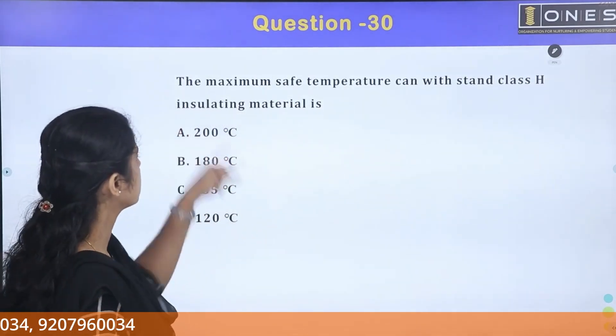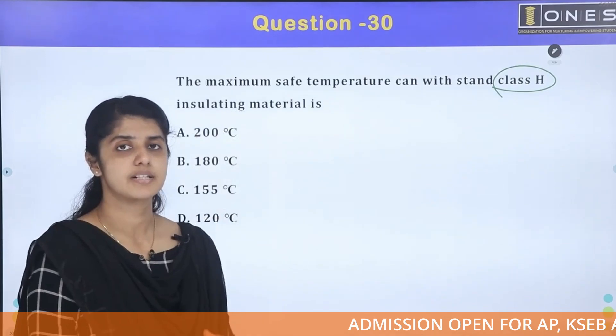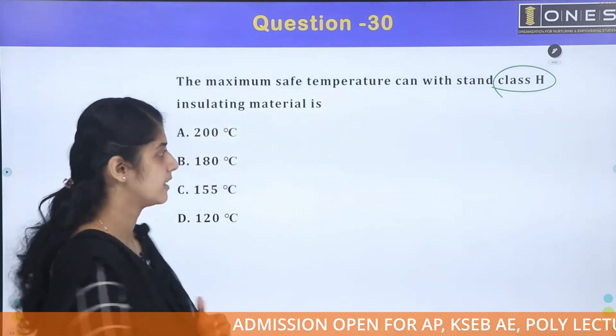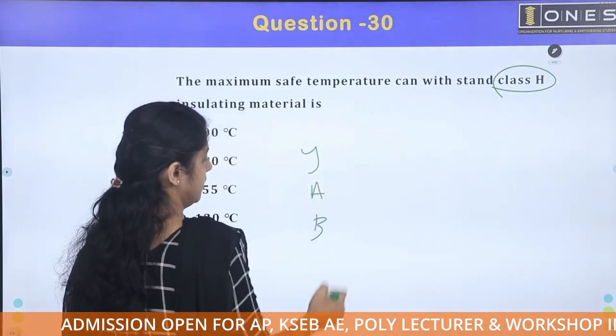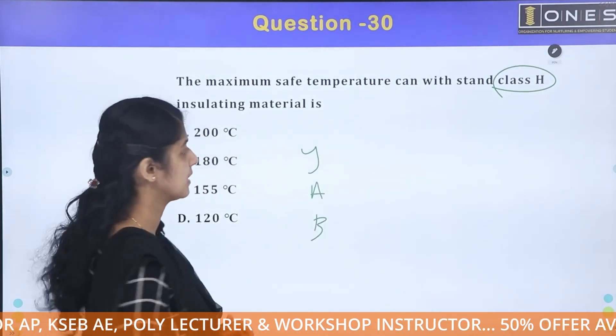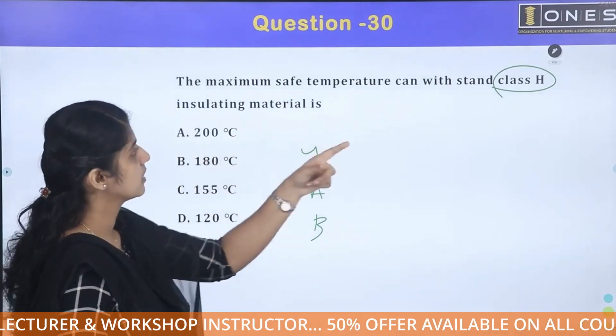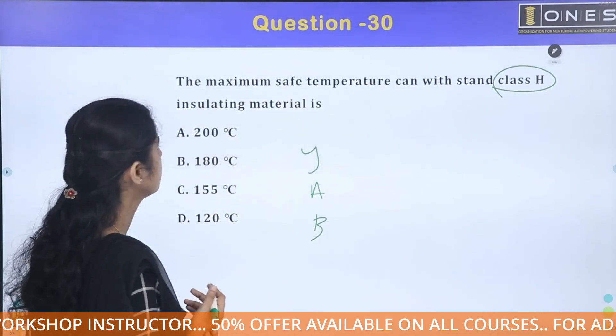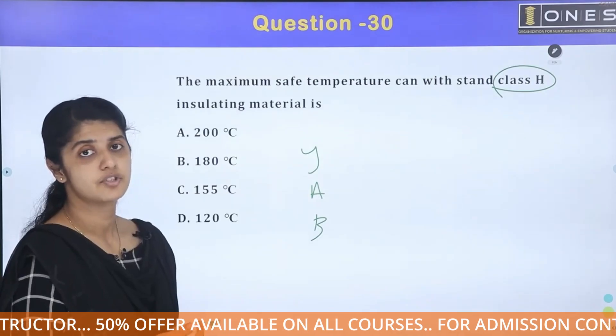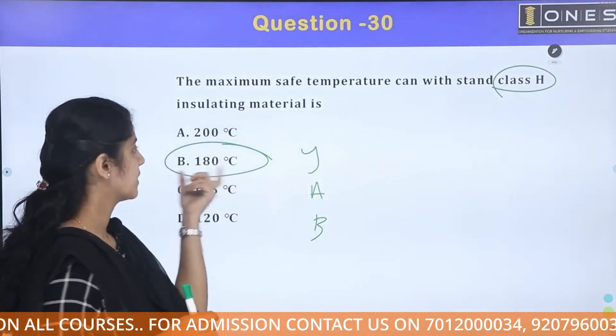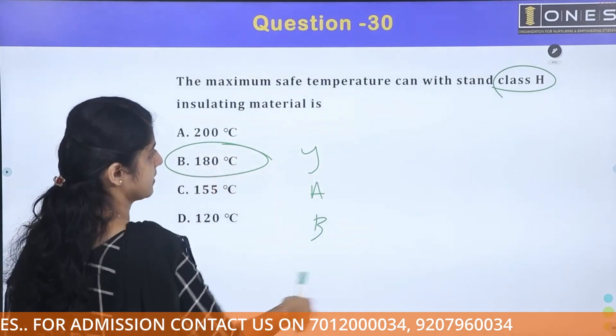The maximum safe temperature that a Class H insulating material can withstand — insulation classes include A, B, E, F, and H. Class H insulating material has a temperature range of 180 degrees Celsius.